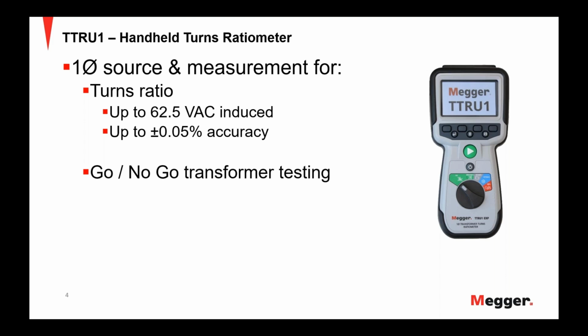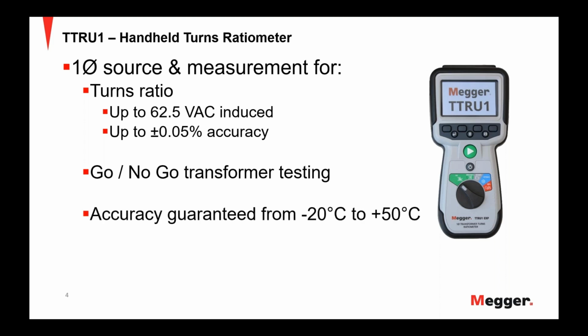We then have that go, no go transformer testing that I mentioned previously, where we look for open circuits and short circuits within the transformer. And when we talk about the transformers, I said 1 or 5 MVA, and that includes single phase and 3-phase transformers, as well as instrument transformers like current transformers and potential transformers. And lastly, the accuracy of the instrument is guaranteed across all of the climate extremes that you may be working in, whether you're in Arizona in the summer or you're in Montana in the winter time. The TTRU-1 will be reliable and give you the results to make better informed decisions about your assets.